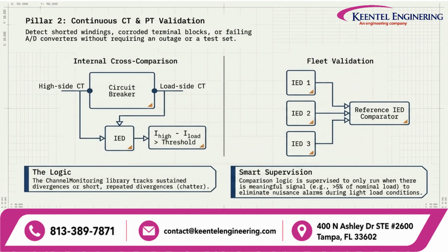The second pillar focuses on continuous CT and PT validation. Through internal cross-comparison and fleet validation, you can detect hardware issues without needing an outage or external test sets.